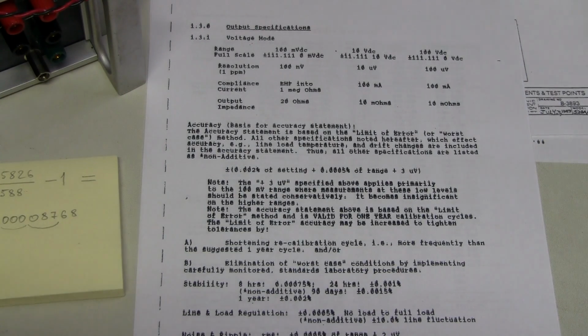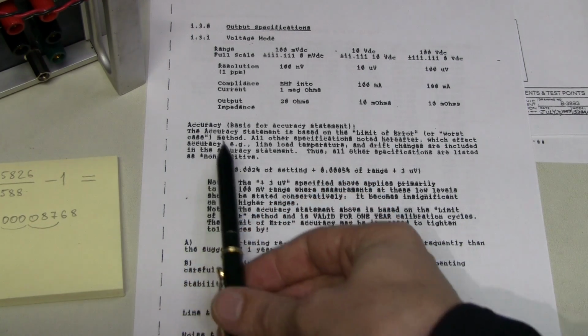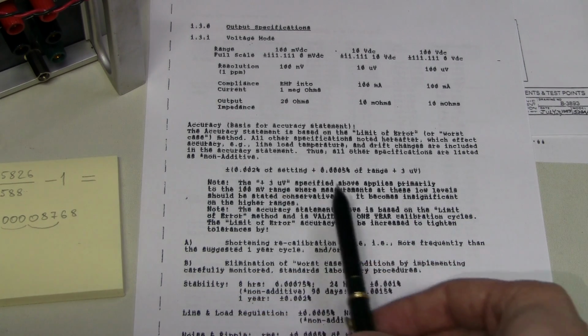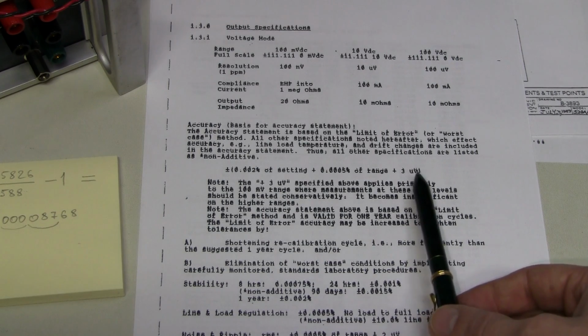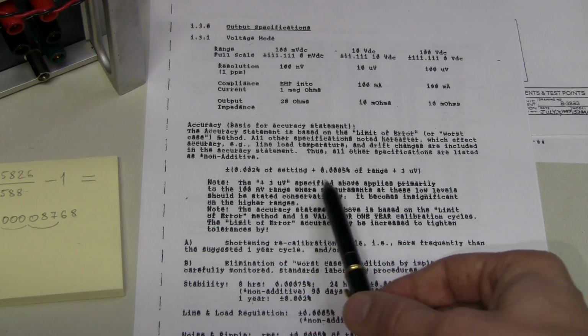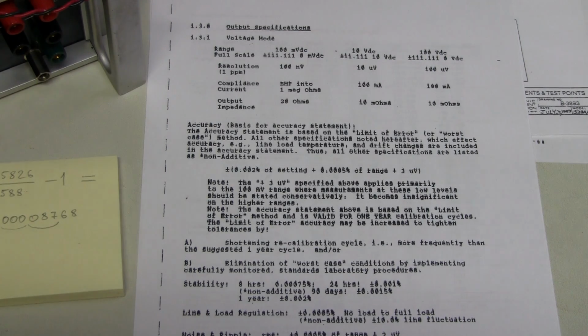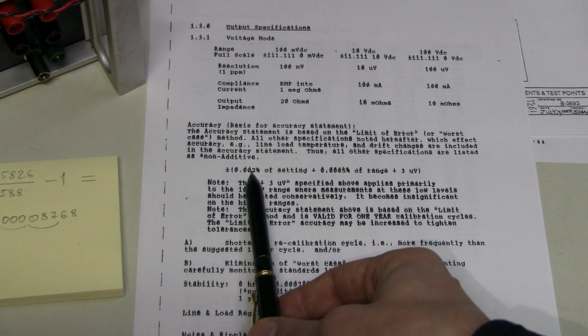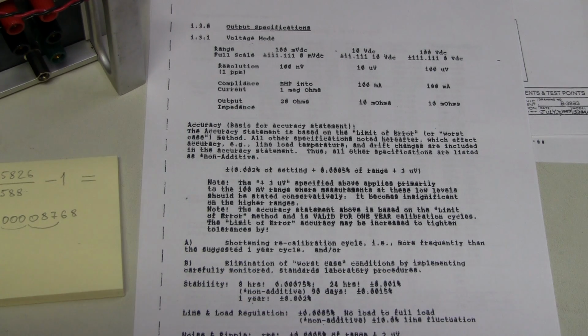And here are the specs for EDC 521. Unfortunately, I don't have specs for 520A. I will have to assume that they are close enough. Perhaps 520A is slightly worse. Let's see. Accuracy here is specified at 20 ppm of setting plus 5 ppm of range plus 3 microvolts. And there is a note that 3 microvolts primarily applies to 100 millivolt range. And because we are not measuring the output but the reference zener diode, I think we need to take this base accuracy of 20 ppm, and the stability for 1 year is also 20 ppm.